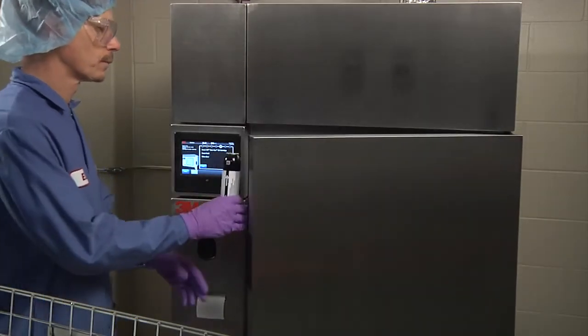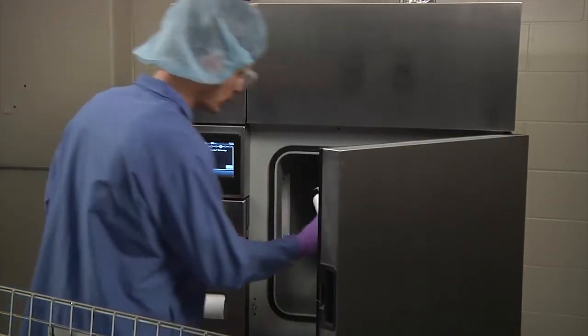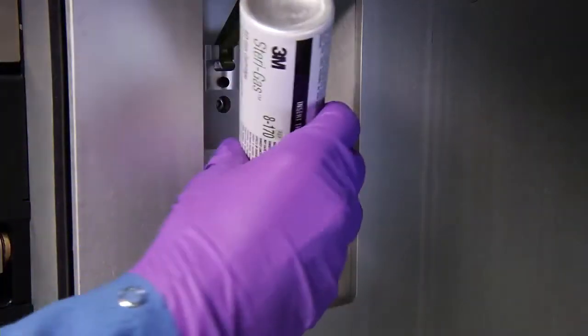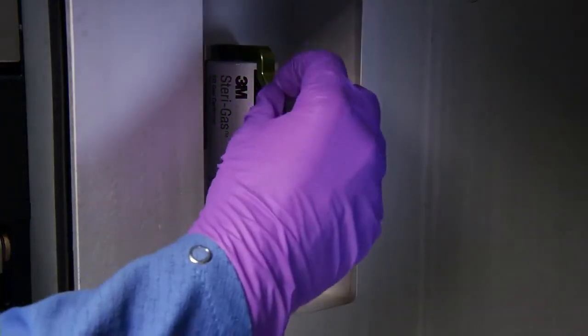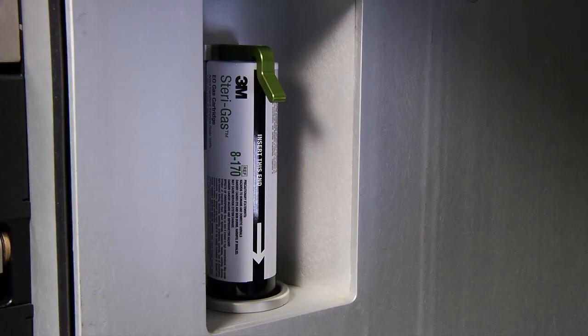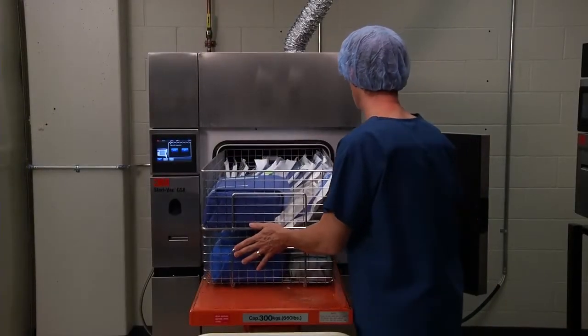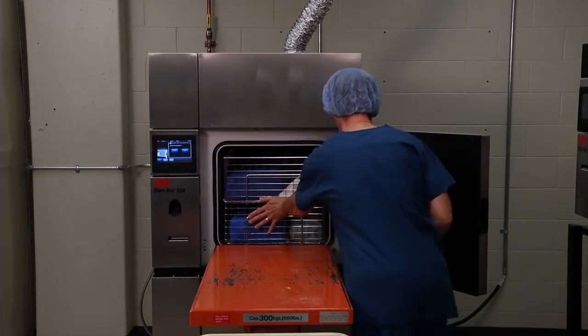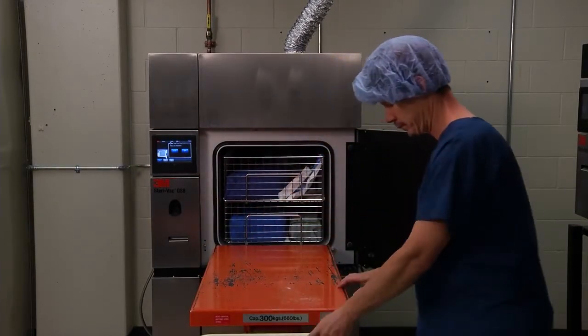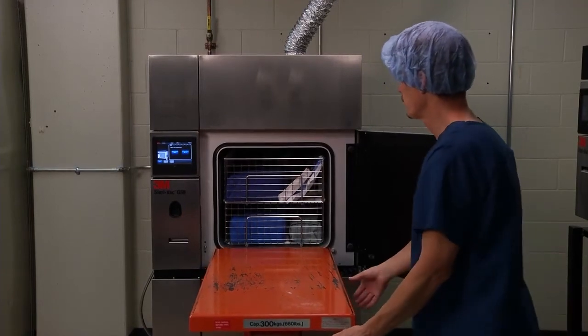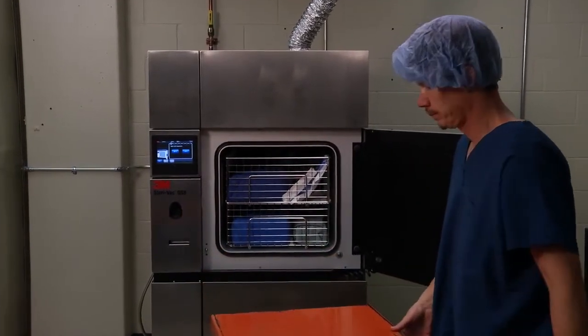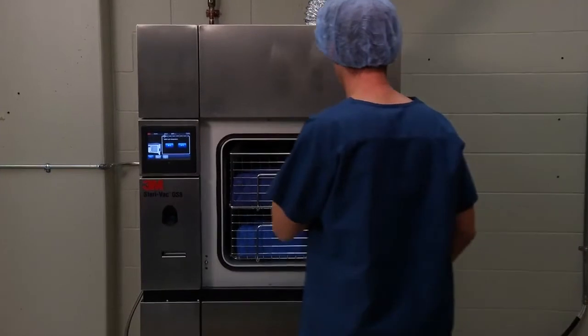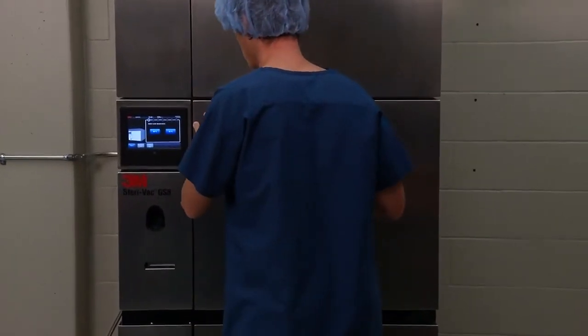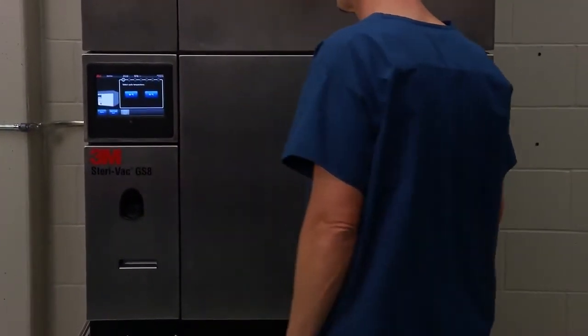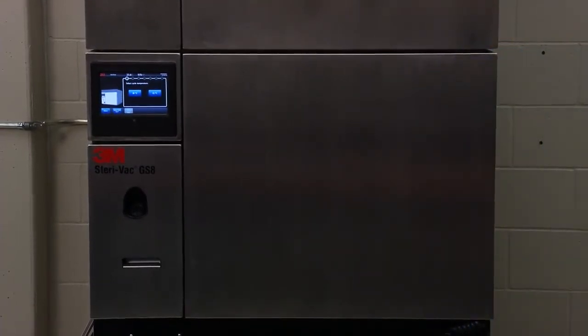Step 5. Place the 3M Steri-Gas EO gas cartridge into the cartridge holder with the arrow pointing downward. Snap the cartridge locking mechanism onto the cartridge to secure it into place. Next, insert the load into the sterilizer chamber. If the load is heavy, be sure to use a cart to help place the load into the sterilizer chamber. Lastly, gently push the door closed until the door seals to the chamber. The touchscreen will display an image of the sterilizer with the door closed.